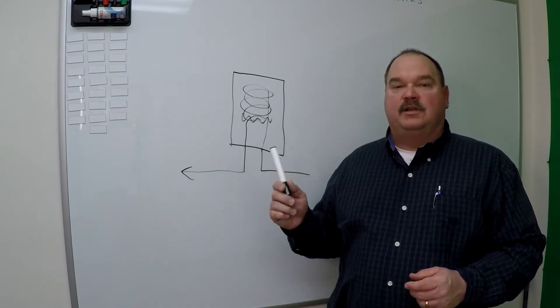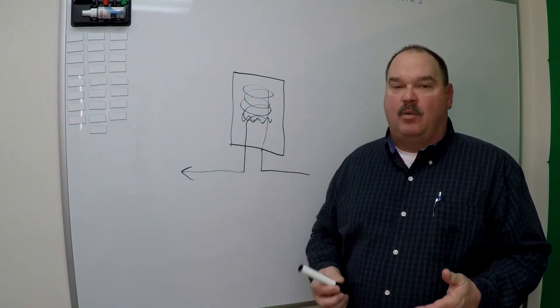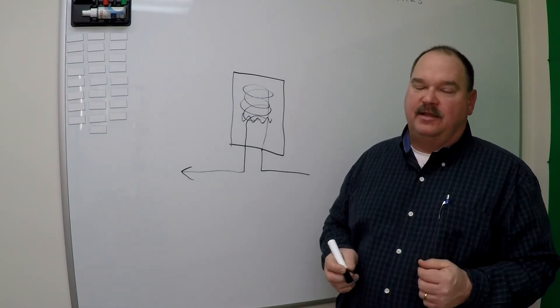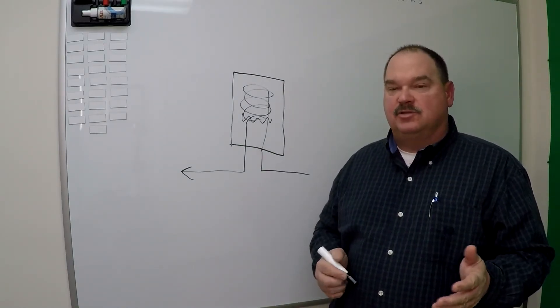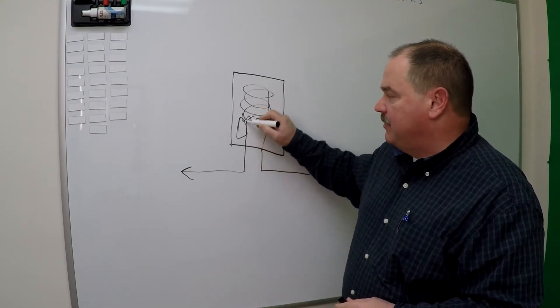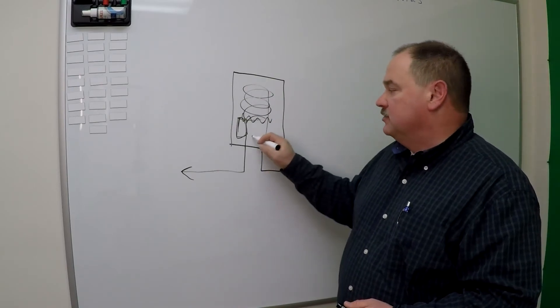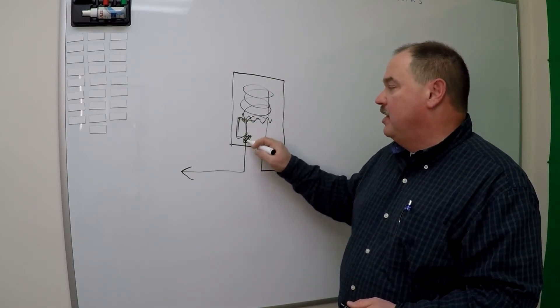Most tankless water heaters have a minimum flow rate required to get them to fire up and make hot water. Usually, that's around a half a gallon a minute. With the Navien tankless water heater, there's actually an internal buffer tank available for the A models. It's about the size of a thermos. It holds one liter of hot water.